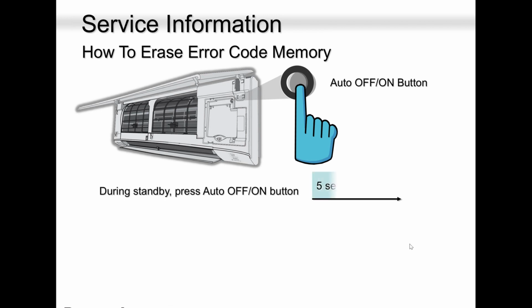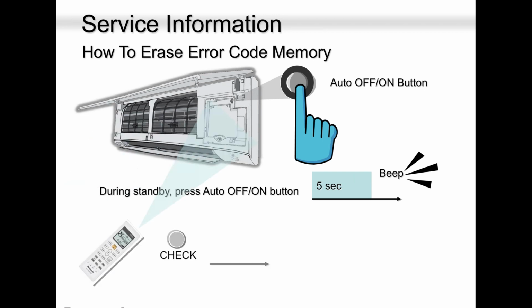When you hear one beep, you go to your remote controller and press the check button once. Just take a toothpick or a prong, whatever, press once. And when you press once, you will hear another beep. So at the unit, you press and hold, you hear a tick. You rush to your remote controller and press the check once, you will hear another tick. You're done. Error code is gone. Error code is clear.